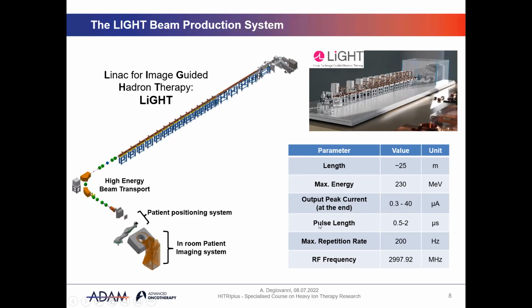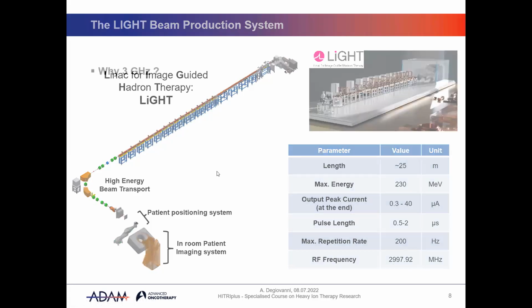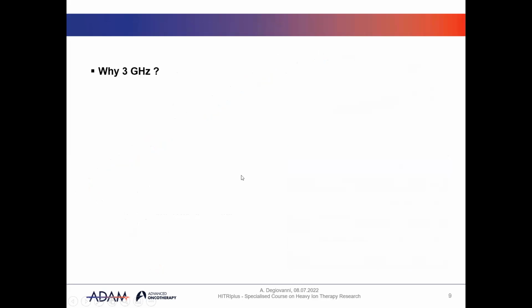A specific feature characteristic of a LINAC machine is the fact of being pulsed. The pulse length is in the order of a couple of microseconds, but there are 200 pulses per second. So that's how we get to what I told you in the beginning, this 1 nanoamp average current, or 6 billion protons per second. All this is achieved by using an RF structure where the radio frequency field has a frequency of about 3 gigahertz, 2,997 megahertz. But one question can be, why 3 gigahertz? What is so special with this number?